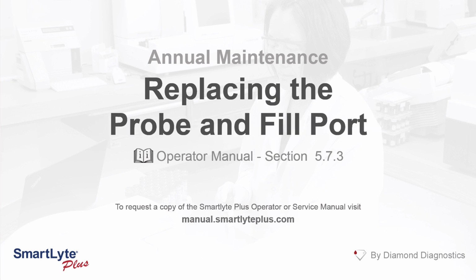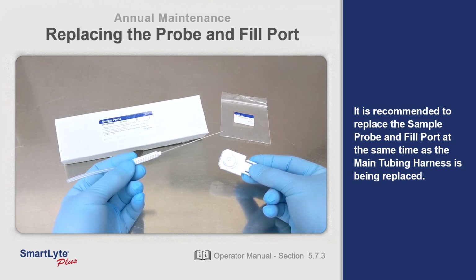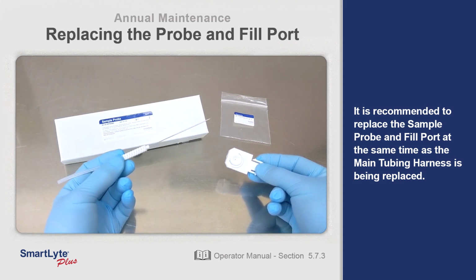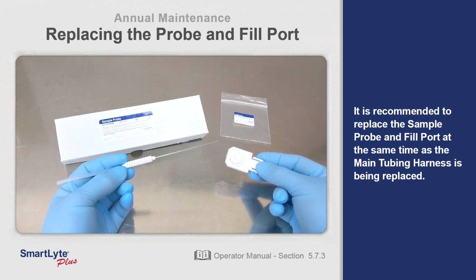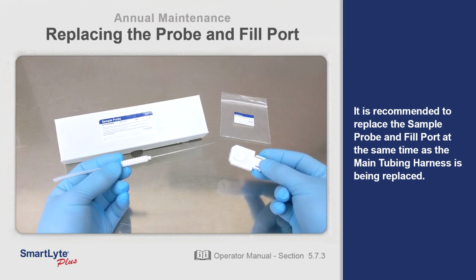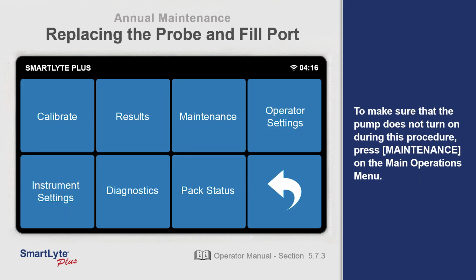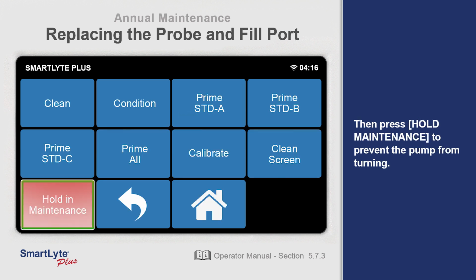Replacing the probe and fill port. It is recommended to replace the sample probe and fill port at the same time the main tubing harness is being replaced. To make sure that the pump does not turn on during this procedure, press Maintenance on the main operations menu. Then, press Hold Maintenance to prevent the pump from turning.